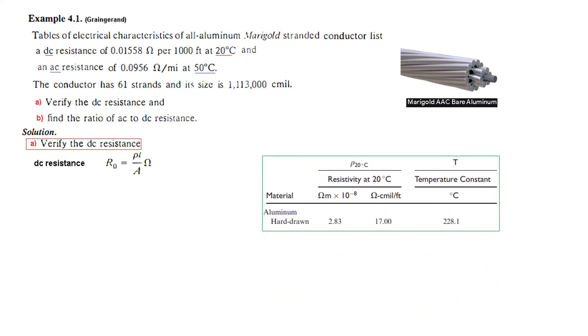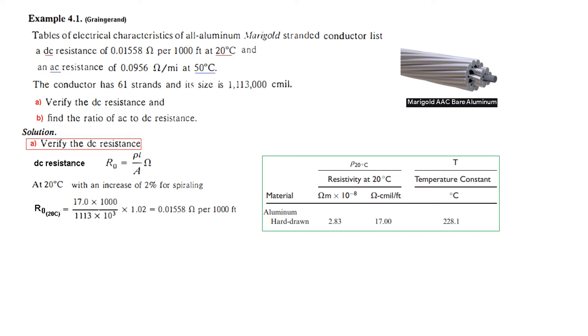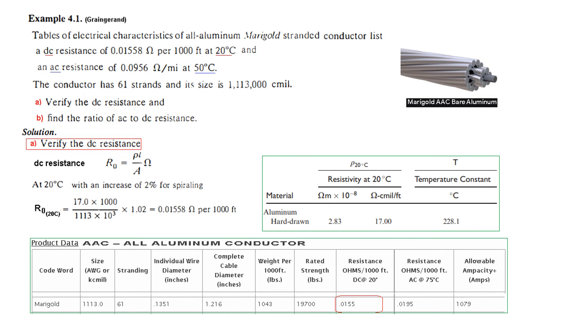From the table, rho at 20 degrees centigrade is given as 17 ohm-cmil per foot. We use L equal to 1000 feet and area equal to 1113 times 10 to the power 3 cmil. Because of the 2% increase in length due to spiraling, we multiply by 1.02. This gives the DC resistance at 20 degrees per 1000 feet, which matches the table value.